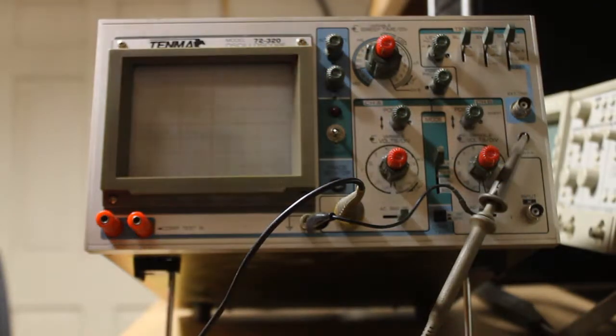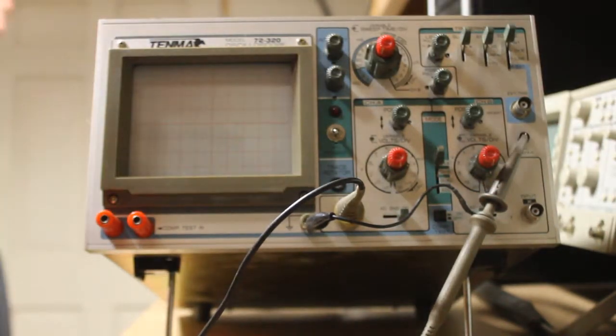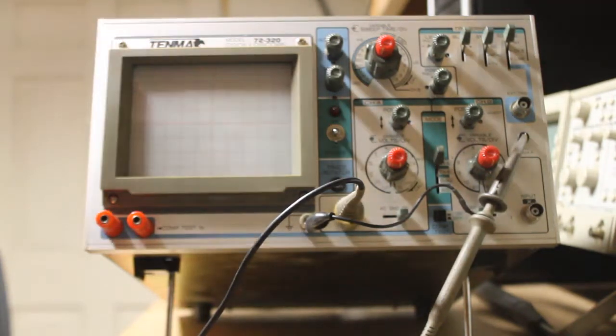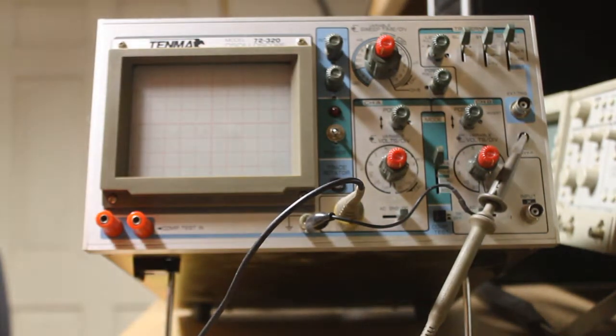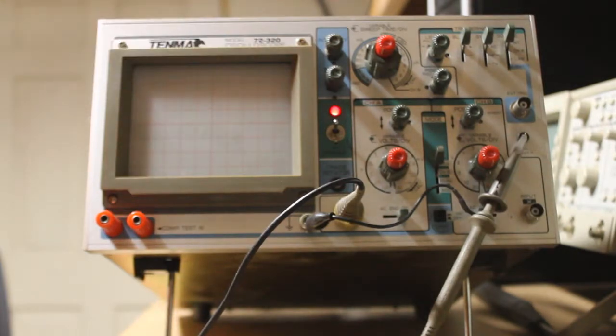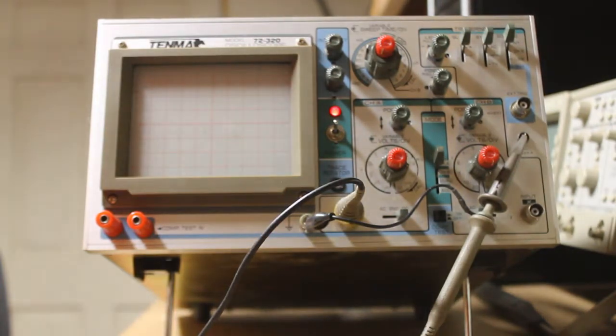We're back. We've finished cleaning all these switches and contacts on the front panel. You don't want to mess with the ones that are internal to the unit. You'll throw it out of calibration, and it can be real bear to get it back in calibration without the correct test equipment. What we're going to go ahead and do is turn the scope on and see if we've corrected the noisy contact issues and the switches, and if we get the correct display on the screen.